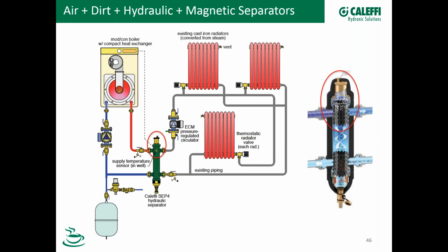And also what that will do is, when you do have a call for heat on that ECM pump that we're showing off to the right there, that whole circuit is already warm, because the boiler is keeping itself warm, keeping the separator and the pipe to and from the separator warm. We see a lot of installers like to use that port that we give you there. We also have a well that you can screw right into that port that'll take a typical 6mm sensor that most of the boilers are using now in their controls. So that gives you, I guess you could call it step 5, if you consider that another function of that device. Yeah, I like that.